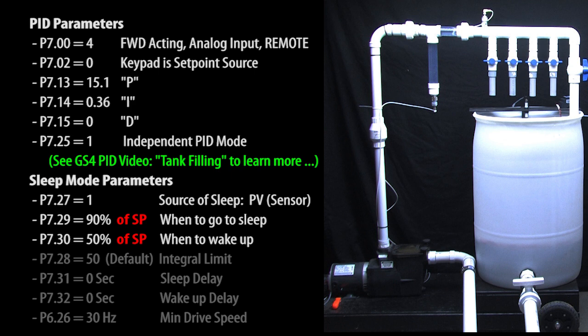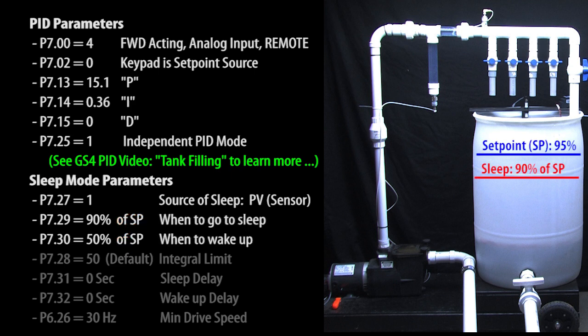So if we set the setpoint at 95% that means the drive will turn the motor off when the water level reaches 90% of the set point, not the tank level. And it's the same for the wake up level. This is 50% of the set point, not the tank level.